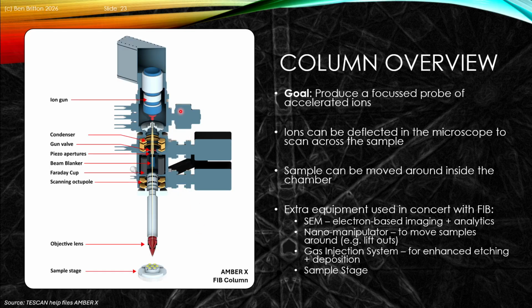So a focused ion beam instrument is established, and the key detail is how the FIB column is working. The FIB column looks in some ways quite similar to an electron microscope. We basically have the source of the ions. We have the so-called ion gun that often sits at the top of the column. And then we have a series of effectively condenser lenses, gun valves, and a few other bits and pieces, as well as some apertures in the system that enable us to down select to a particular probe current.